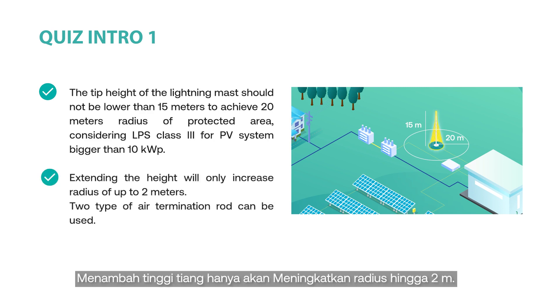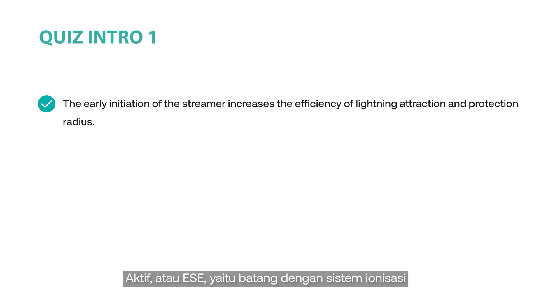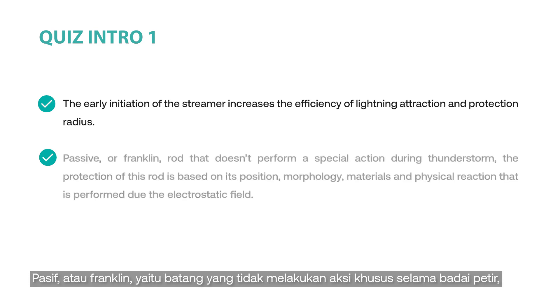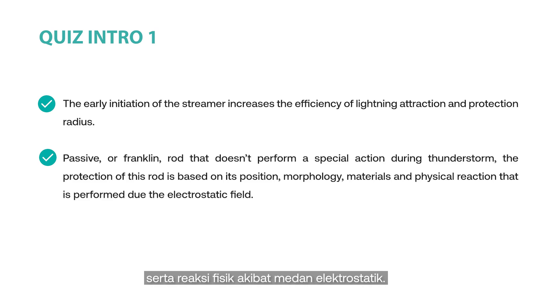Extending the height will only increase the radius by up to 2 meters. Two types of air termination rods can be used. The first is the active or ESE rod with an ionization system that is activated by the electromagnetic field produced by the storm, leading to the creation of an upward streamer. The early initiation of the streamer increases the efficiency of lightning attraction and the protection radius, providing a larger radius compared to its passive counterpart. The second is the passive or Franklin rod, which does not perform special action during thunderstorms. The protection of this rod is based on its position, morphology, materials, and physical reaction due to the electrostatic field.